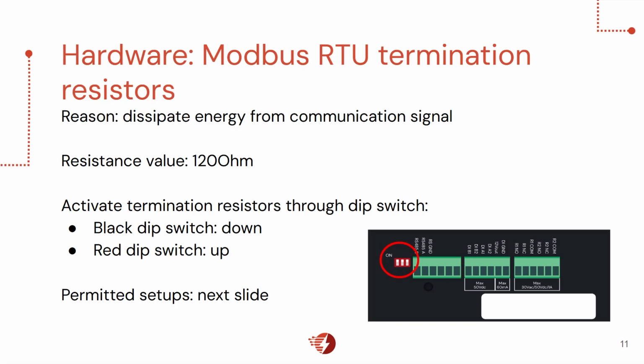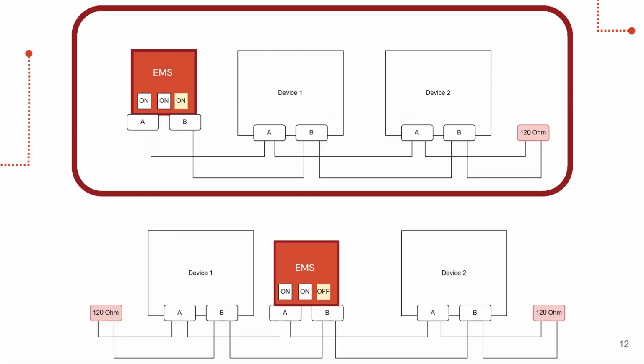So there's a little switch that tells you which is on, which is off. Do not mind the black dip switches, these are for the older models. All the new ones have the red ones with 'on' written on them. Here's an example of how it's actually set up. It has to be at the beginning of the chain with an end resistor of 120 ohms, which you need to put yourself at the end.